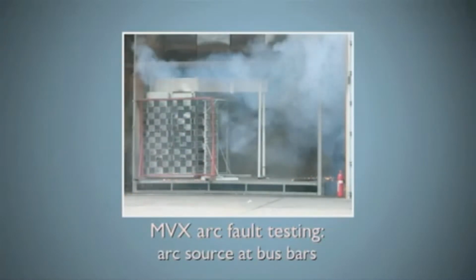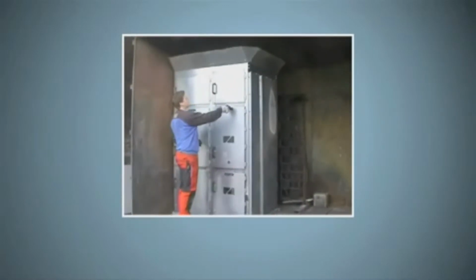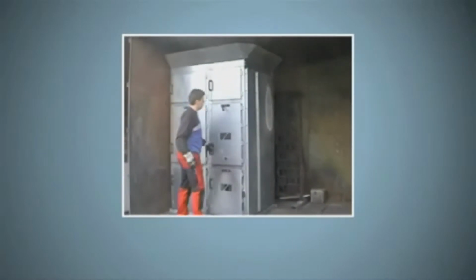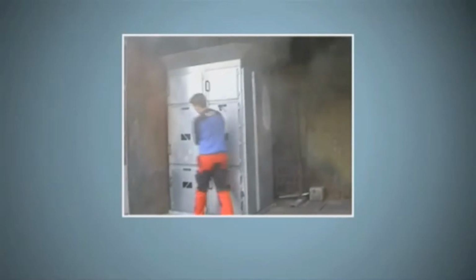The compartment sidewalls protected LV sections from an arc fault in the MV section and would have protected any operators from harm. Note that the panels are scorched but not compromised. LV sections are entirely clean and unaffected by the arc event.